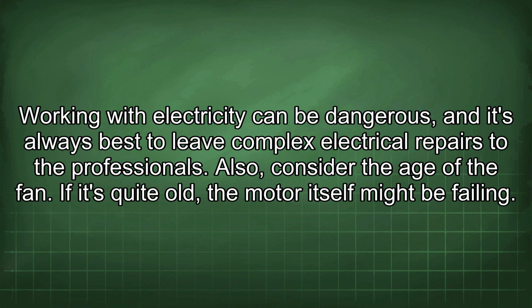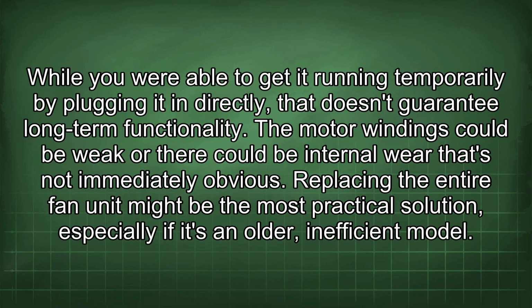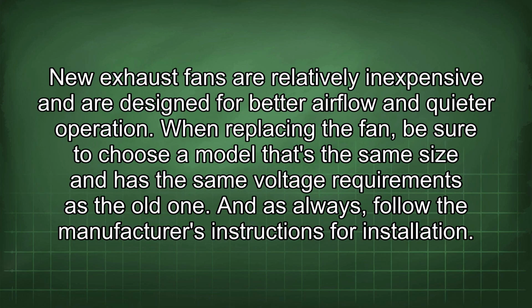Also, consider the age of the fan. If it's quite old, the motor itself might be failing. While you were able to get it running temporarily by plugging it in directly, that doesn't guarantee long-term functionality. The motor windings could be weak, or there could be internal wear that's not immediately obvious. Replacing the entire fan unit might be the most practical solution, especially if it's an older, inefficient model. New exhaust fans are relatively inexpensive and are designed for better airflow and quieter operation. When replacing the fan, be sure to choose a model that's the same size and has the same voltage requirements as the old one. And as always, follow the manufacturer's instructions for installation.